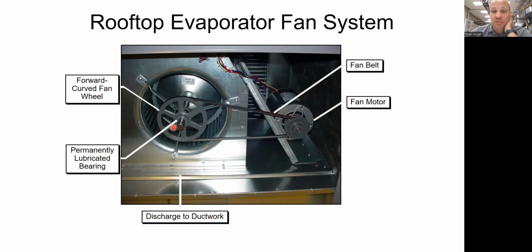That has changed with some of the newer fan designs, but a fan that's designed like this, a forward curve fan, or sometimes called a squirrel cage blower, is almost always going to be belt driven in order to get that extra torque and that extra capacity out of that guy. These pulleys can be changed to different sizes, and doing so would yield a different amount of airflow in the space. So this is the one that comes with it.